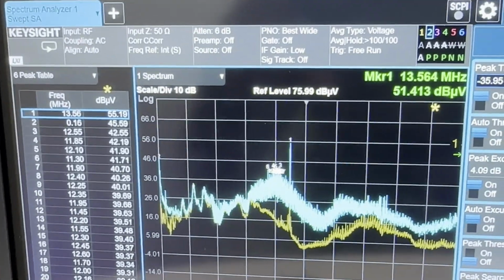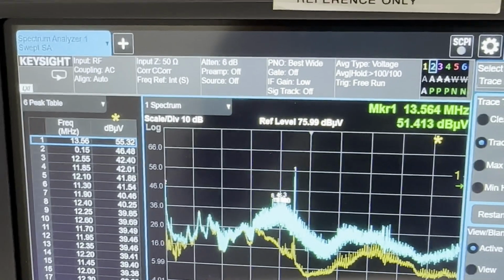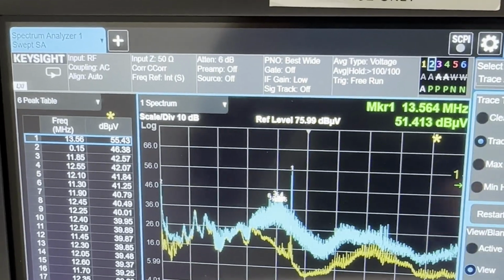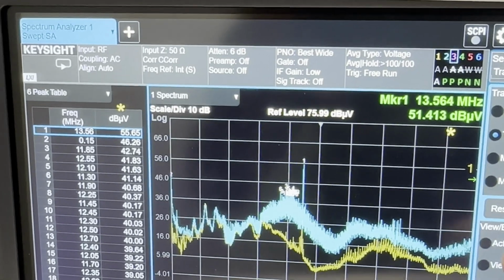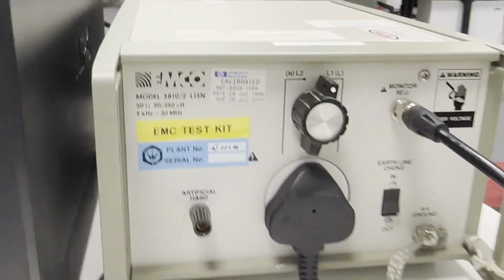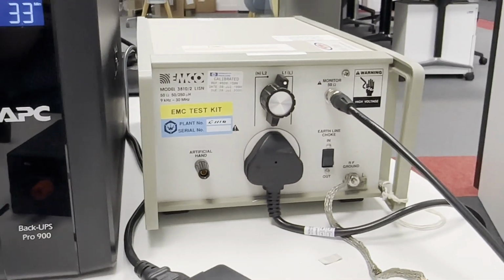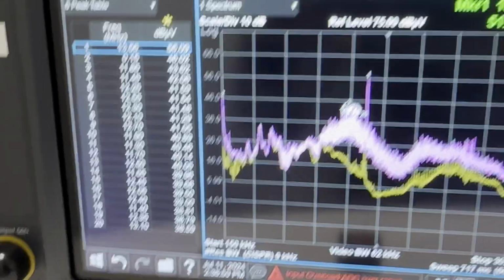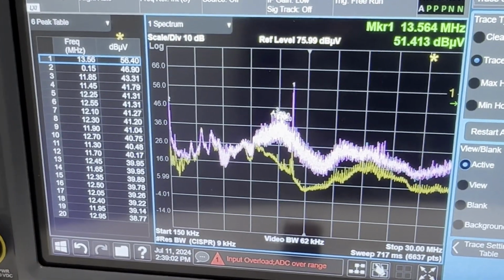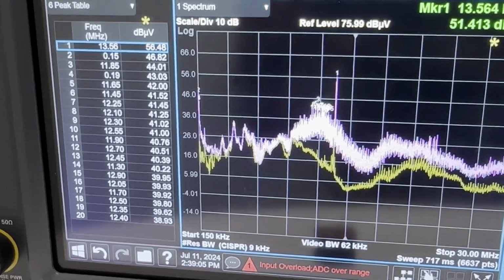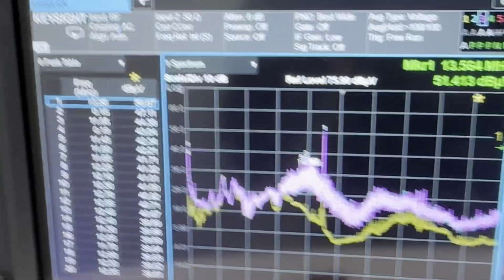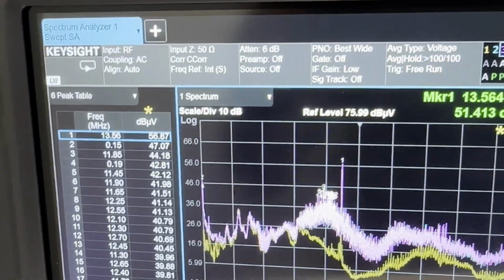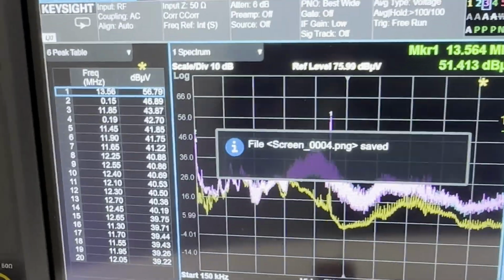And then what you can also do, you can set that trace to view, select trace 3 and switch the LISN from one conductor to the other. So that's the second conductor now. And you can see it's not all too different whatsoever.